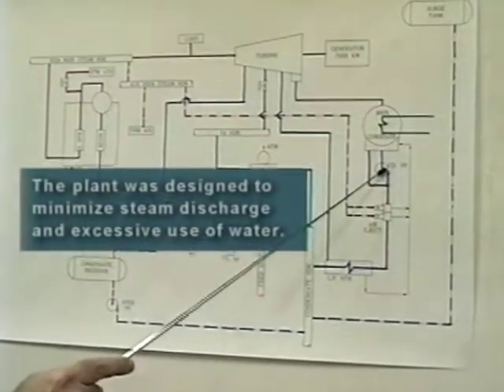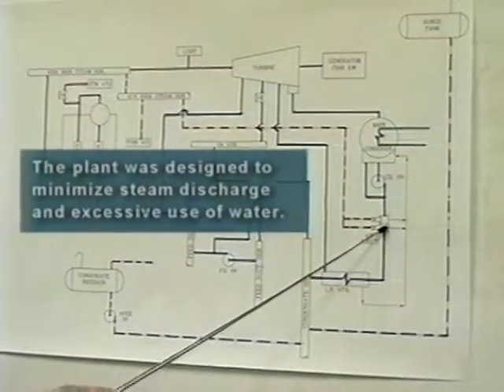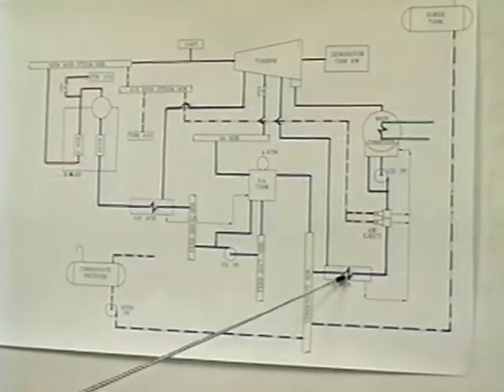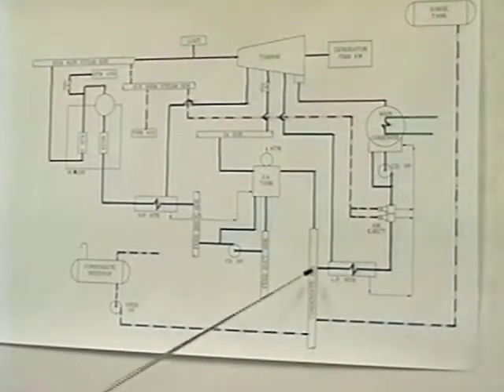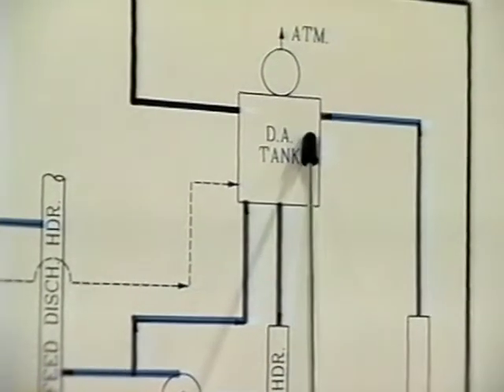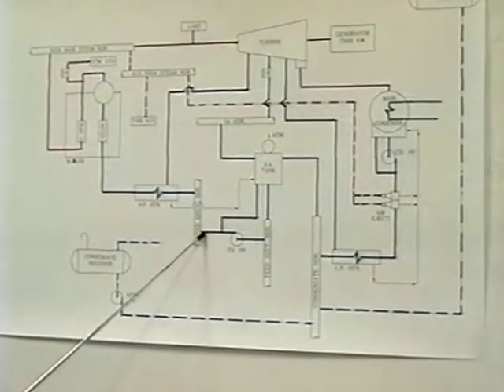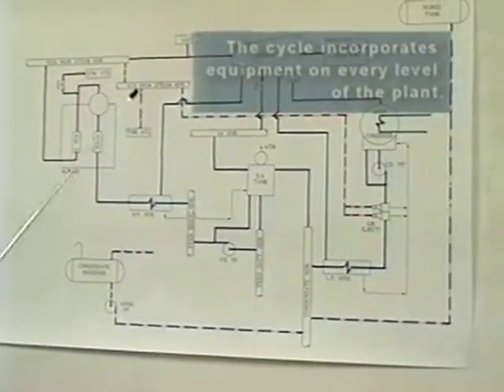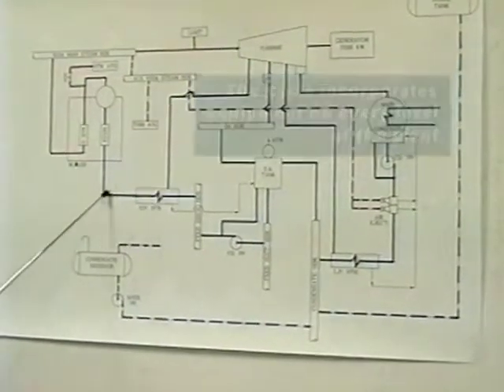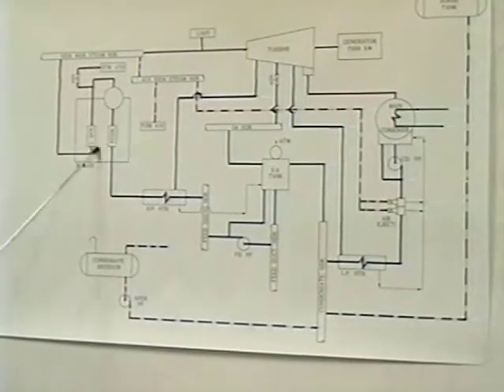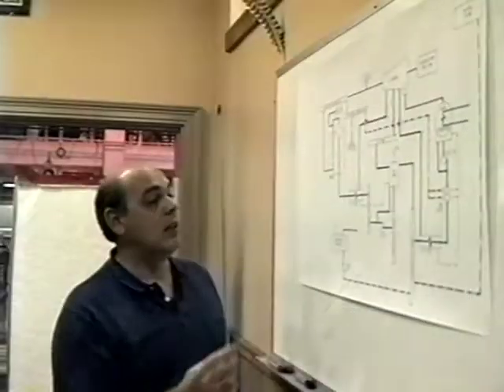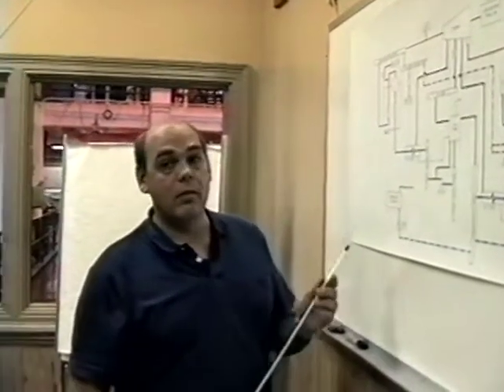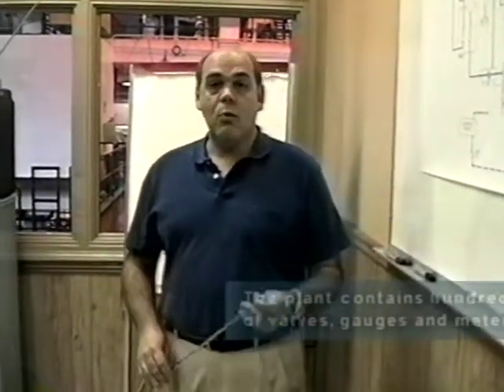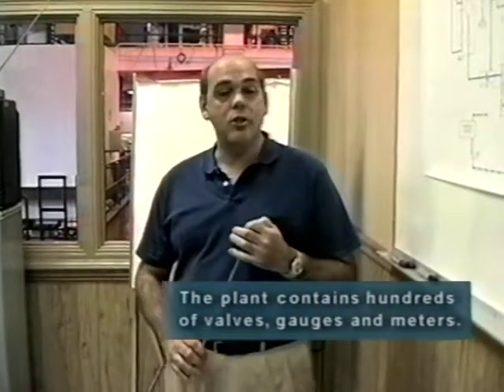The condensate pumps take suction out of the condenser hot wells, run it through the air ejector condensers, through the first stage heater or low pressure heater, LP heater, into the DA tank or deaerating feed water heater. The feed pump takes suction and pushes the water at about 800 to 850 pounds per square inch through the HP heater, back through the boiler, through an economizer, which is a last stage heater. This concludes the cycle. Now let's take a walk through Pierce Station so I can show you the actual components.